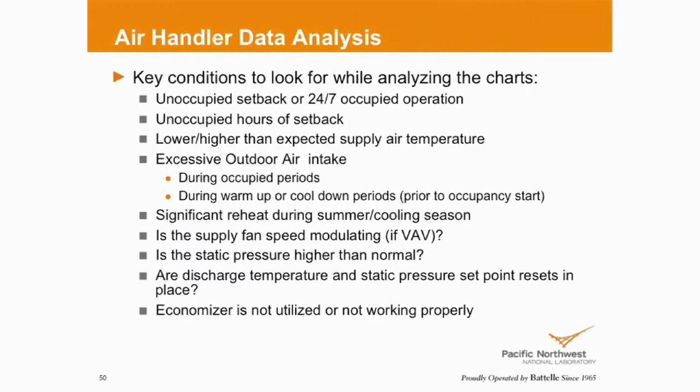Do we have the economizer when the fan starts up at 4 in the morning or whatever time we start up, because it takes 2, 3, 4 hours to get the space cooled back down or warmed up? So when we're doing that, is the economizer going back to minimum position, 20, 25%, 10%, whatever it is? Why are we ventilating the building on a morning warm-up or cool-down?